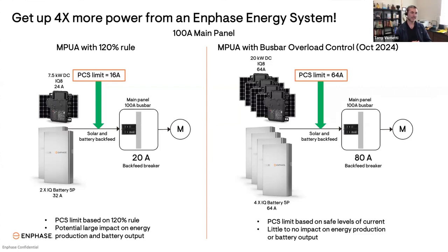With Busbar PCS, the customer can have a 20 kilowatt PV system and a 20 kilowatt hour battery with 4 of the IQ Battery 5Ps and still be able to get the full power from both the PV and the battery system.